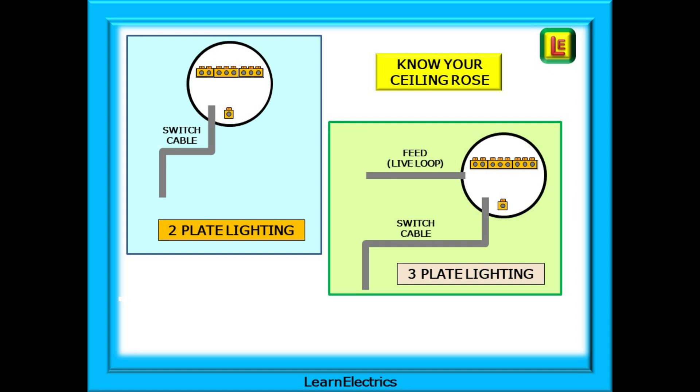In a two-plate system there will only be one twin and earth cable entering the ceiling rose and that is the switch cable coming from the switches. For a three-plate system there will be two twin and earth cables: a switch cable from the switches and a feed cable from the consumer unit.